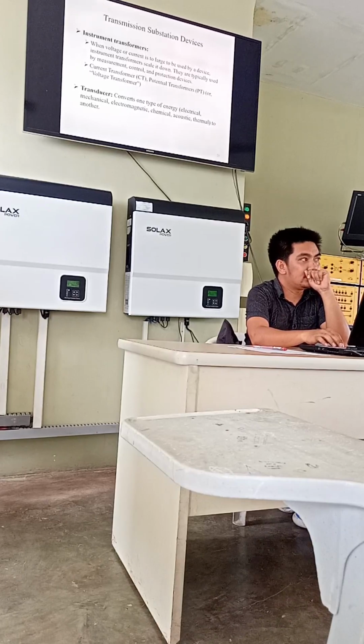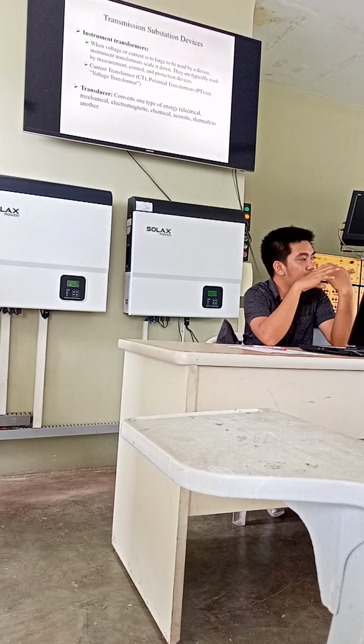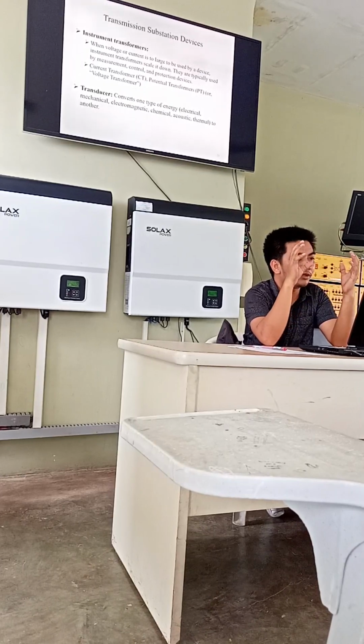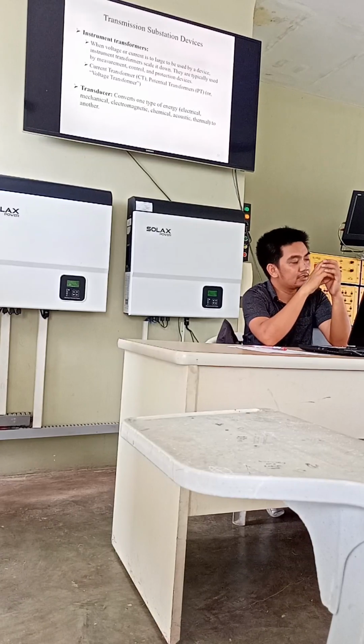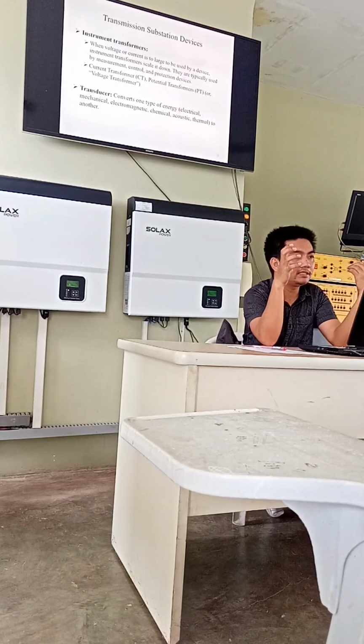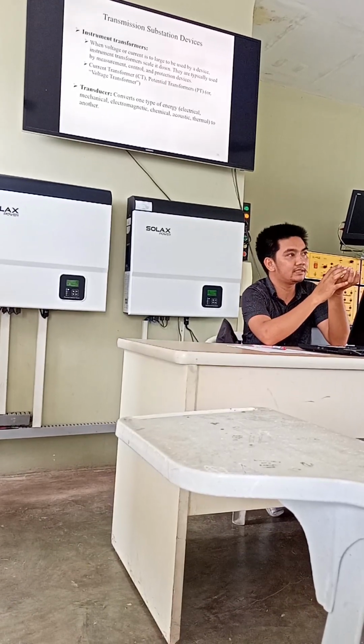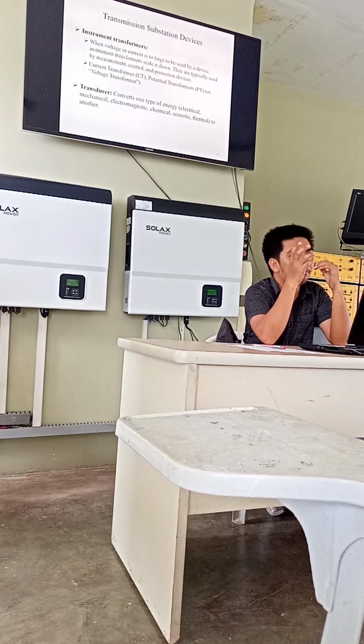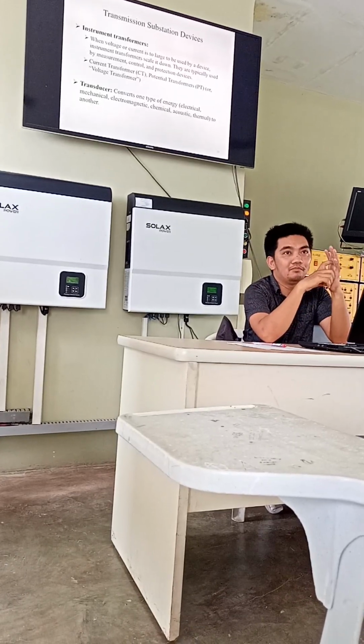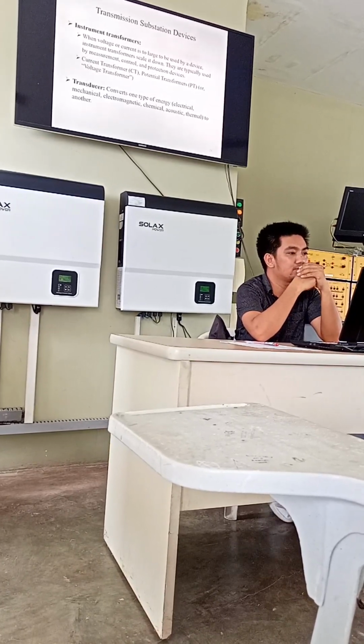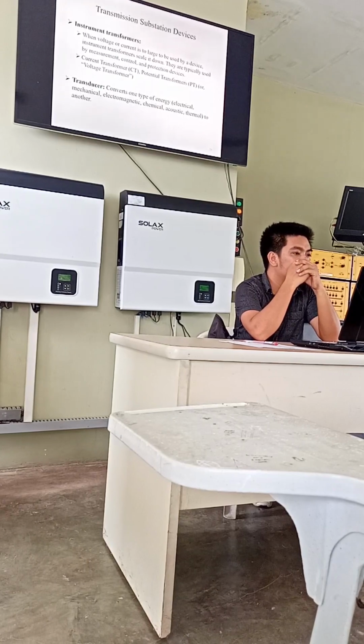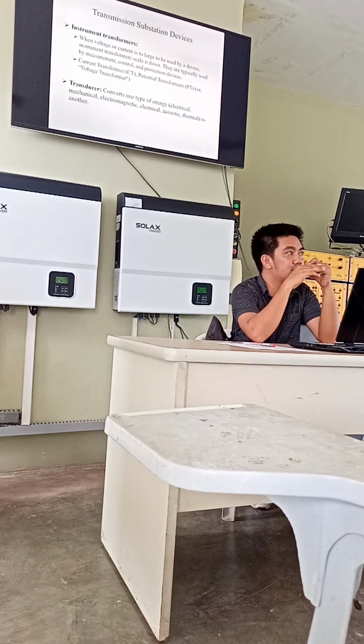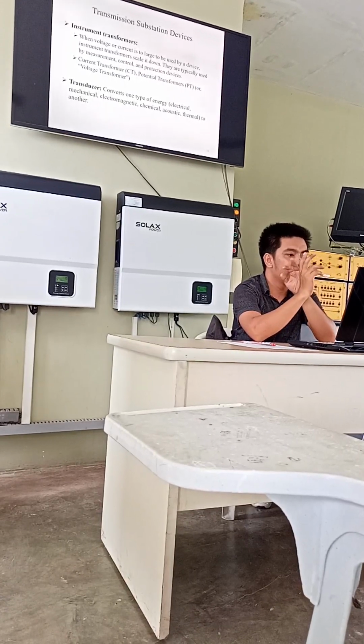Instrument transformers, basically the CT and the PT, current transformer and potential transformer. Because the substation operates at the highest voltage and high currents, we need to monitor that. To monitor it, we need the CT and PT to reduce it to a readable voltage and current level for measurement devices like relays. So you can't directly measure 13.8 kV directly at the relay. We need to transform it first using an instrument transformer. There are a lot of these, called transducers. Instrument transformers, the common one is CT and PT.